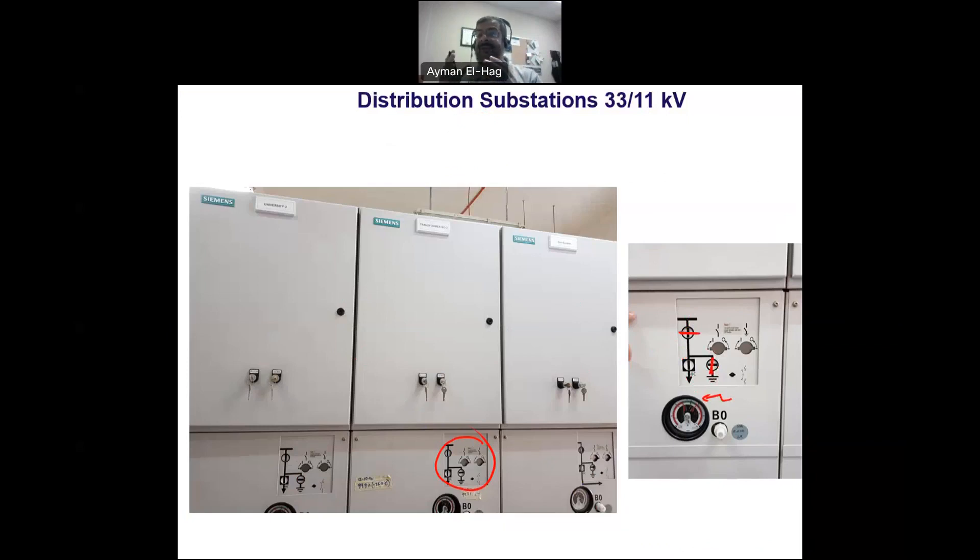Here is a gauge for the SF6 pressure. If there is any leak, it will go to a low level, which is not good because this will reduce the insulating property of the SF6. If there is a fault inside, the pressure will go to a high level. Between these two red lines is the green zone, which is the allowed pressure of the SF6.